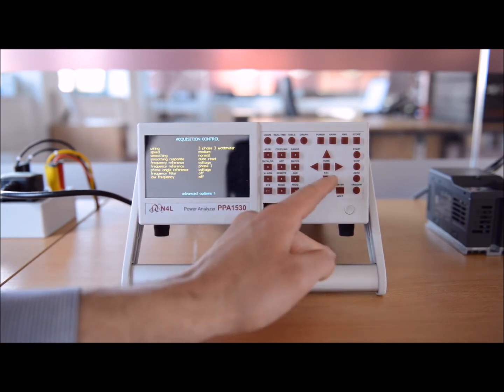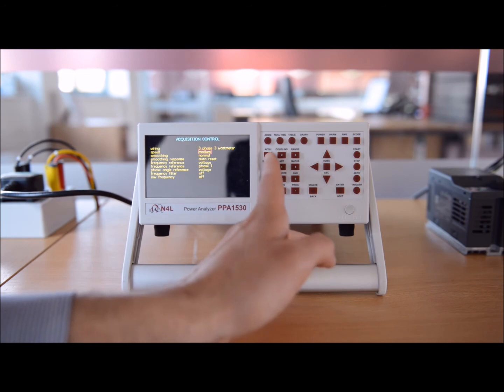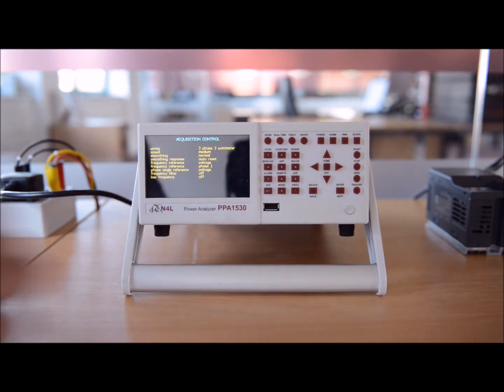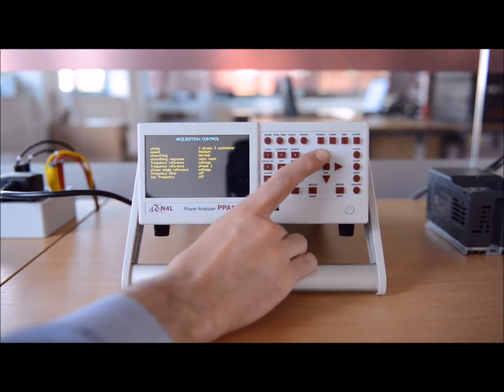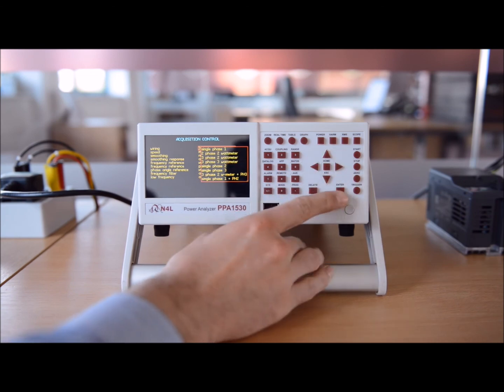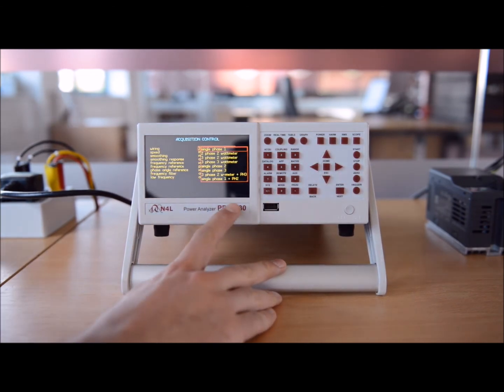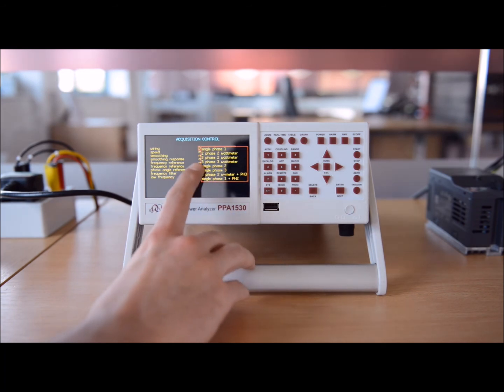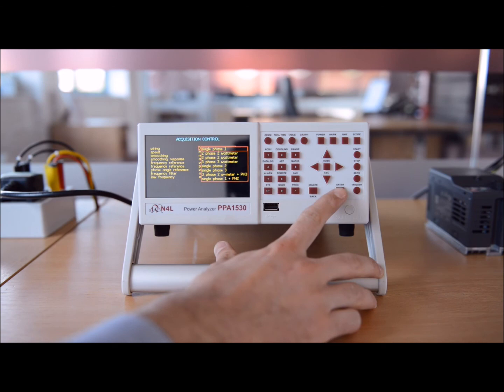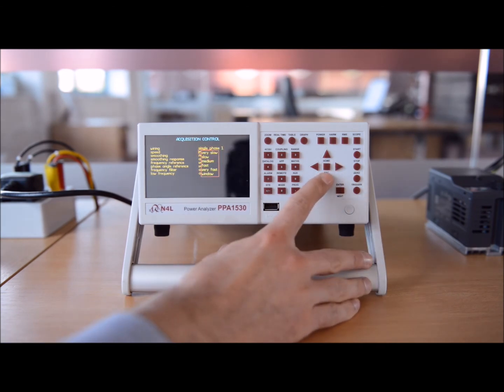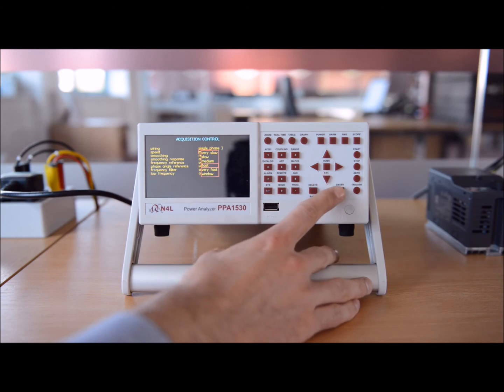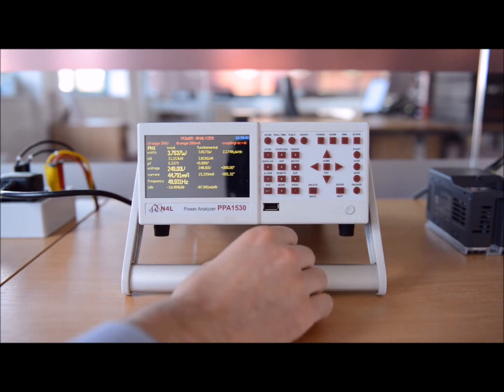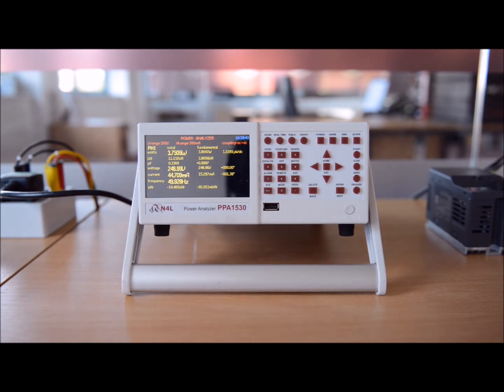Okay, so one other thing to basically take note of is in the acquisition menu, what we can do is set up the instrument to be optimized for our setup. Now, normally you would probably purchase a single phase analyzer if you're only going to be doing single phase input measurements, but on this occasion we're actually using a three-phase analyzer for a single phase application at the input. So what I'm going to do is change it from the default three-phase 3 watt meter to the single phase 1, and also I'm going to change the speed because the medium update rate is okay, but I want a bit faster measurement today. So let's move it to fast initially and see how we get on. Everything else can stay as standard. There's nothing else to change for a 50 Hz, 240, 250 volt internal shunt measurement.